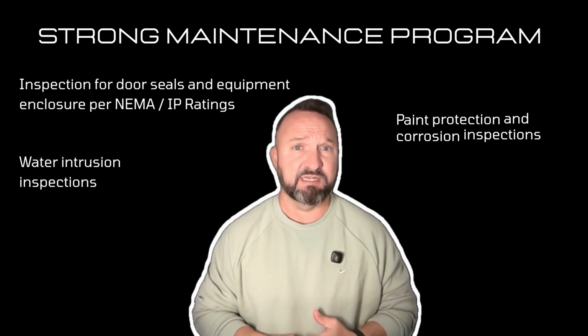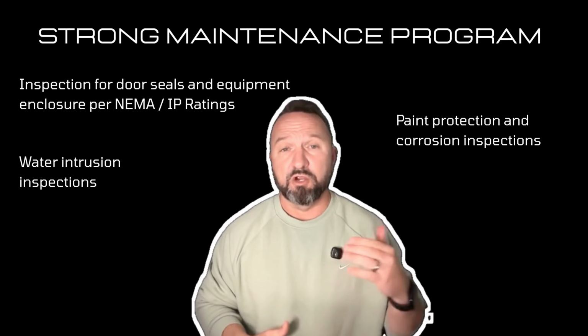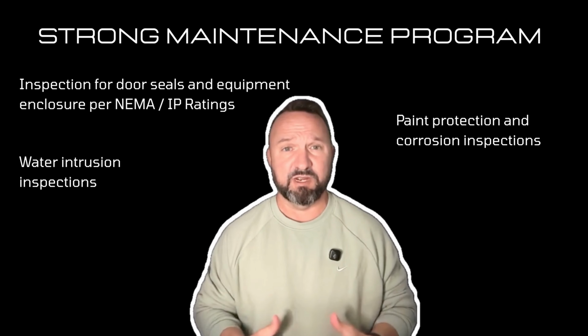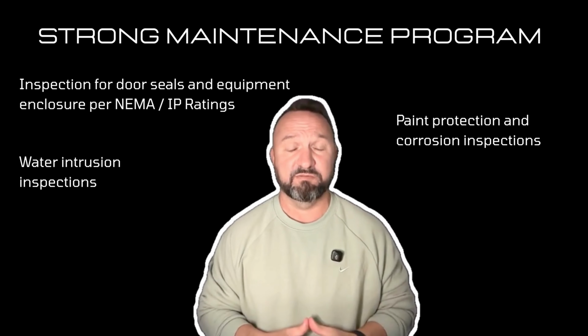Another thing that comes into play is the dust, moisture, and corrosion, which accelerate equipment failure. Once again, this equipment is out in the elements, could be hot, could be cold, snow, rain, ice. Maintenance has to include inspections of the door seals, enclosure condition checks, making sure there's no signs of leakage or water intrusion, corrosion control, especially if it's around the coastlines or high corrosive environments, and environmental monitoring for these systems. The better the environment, the longer the equipment can live.